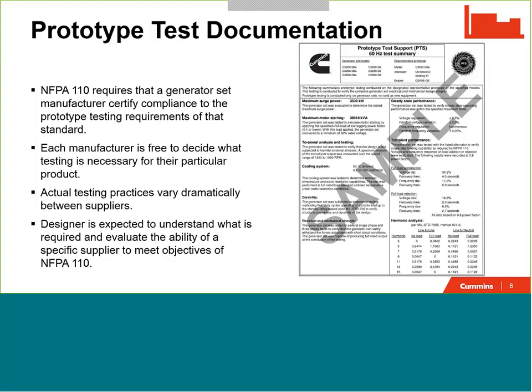However, although NFPA 110 does require the generator set manufacturer certify compliance to certain testing requirements, each manufacturer is free to decide what testing is actually necessary for their product. And so as a result, actual testing practices amongst manufacturers vary dramatically. Although NFPA 110 might say that short circuit testing is a requirement for a prototype test, different manufacturers may conduct that same testing in different ways. And so ultimately it is up to you, the designer, to understand what is realistic and what should be required, and to evaluate the ability of a specific supplier or any supplier to actually meet those objectives as outlined in NFPA 110.